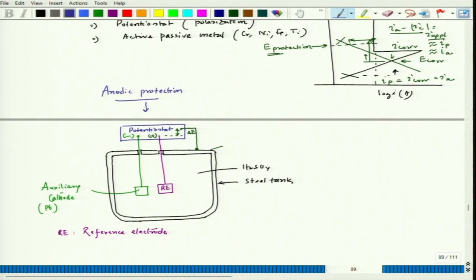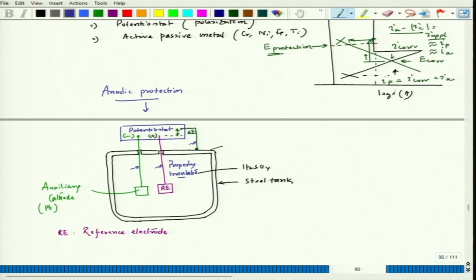Interestingly here, these wires need to be properly insulated. Otherwise they can also corrode in the presence of H₂SO₄ and can affect those auxiliary cathode as well as the reference electrode. So proper insulation is required to avoid galvanic cell formation.